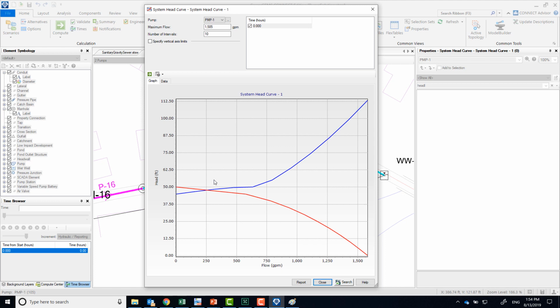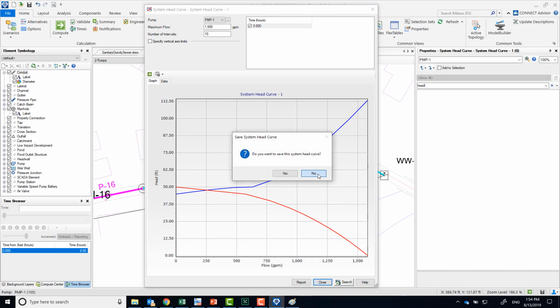Because now we're basically shoving more flow, a combined flow of 661 gallons per minute through that 8-inch pipe, and there's a lot more friction, so each pump generates a pump head of 49 feet. So it doesn't really seem that useful, right, to have 2 of them at the same time.